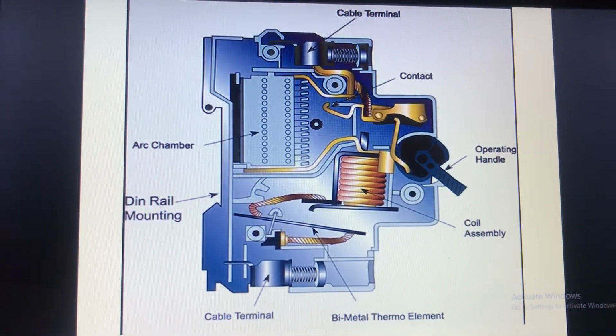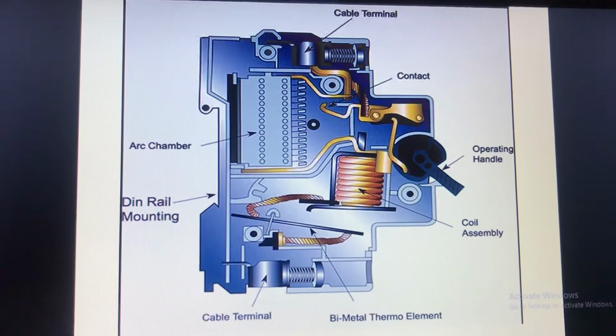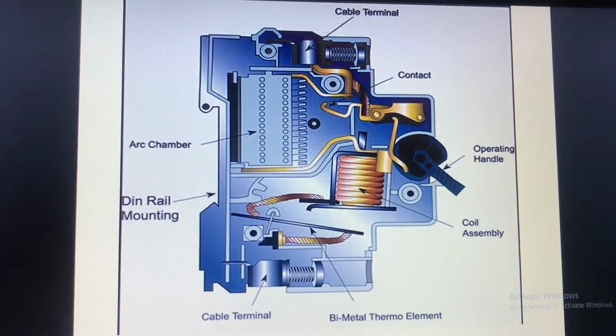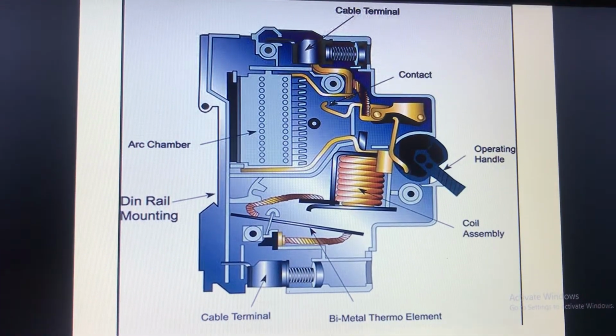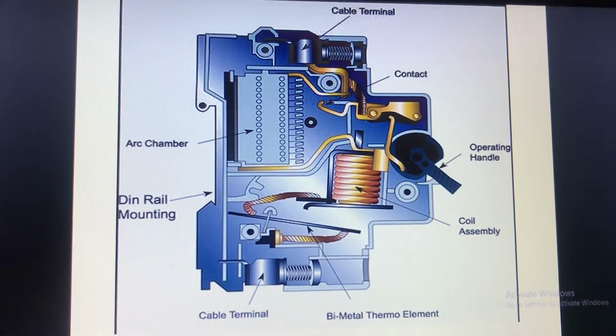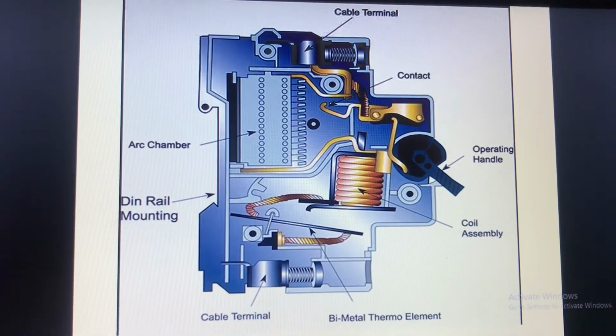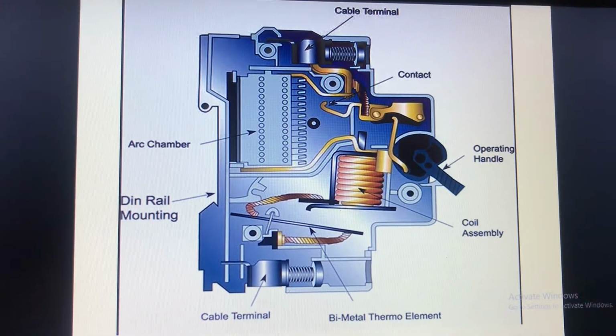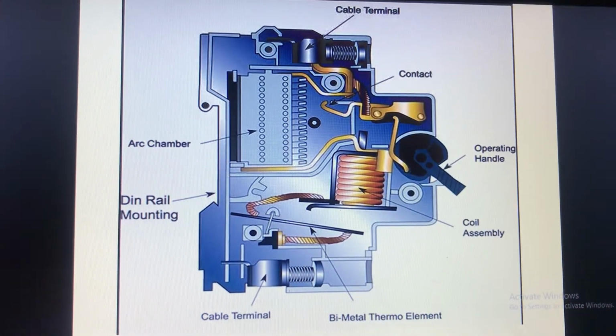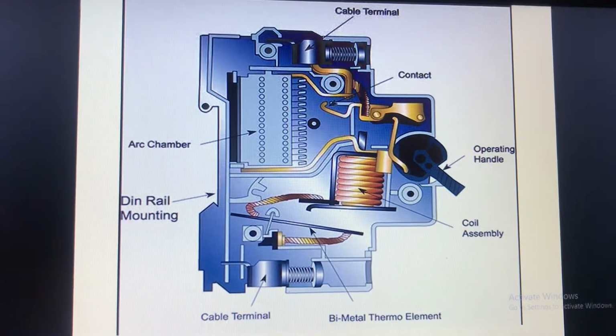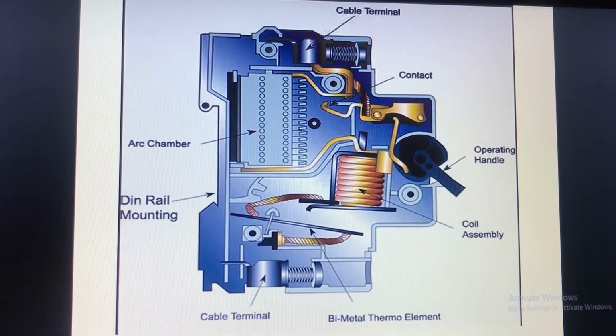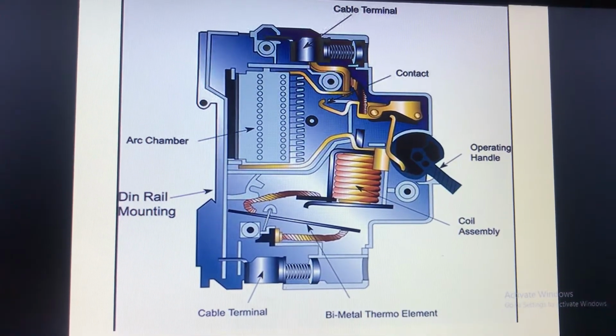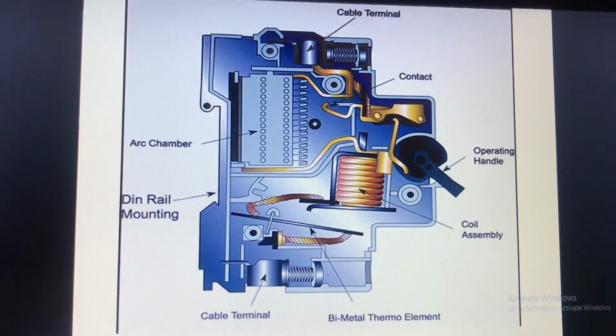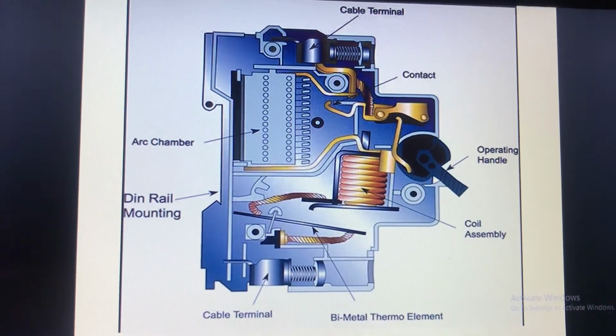So you can see there are two basic elements. One is the coil assembly and other is the bimetallic strip. Coil assembly is for short circuit and bimetallic strip is for overloading conditions. Because in case of overloading conditions, the current which flows through the circuit is nearly double the times or more than this, but not so high as in the case with short circuit conditions. In short circuit conditions, current is very high. It may be 6 to 7 times of the normal rating.